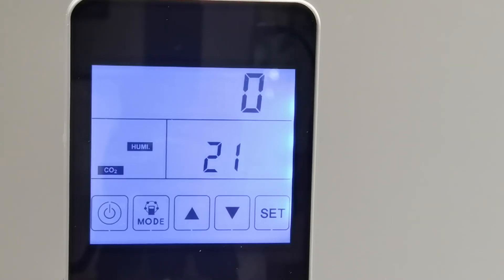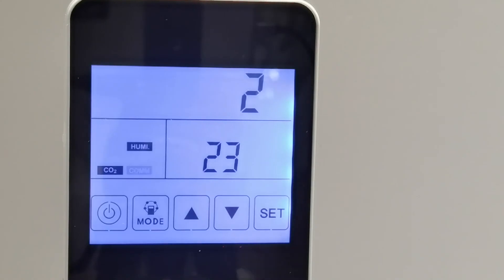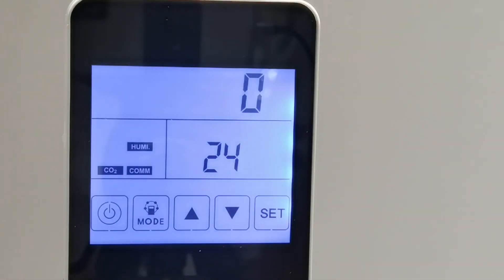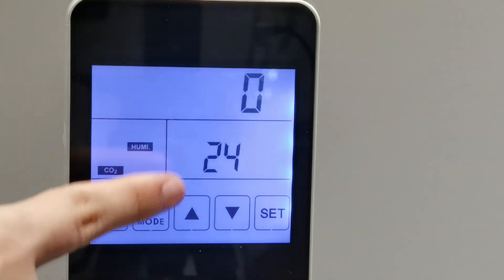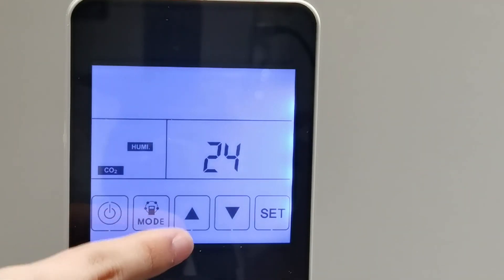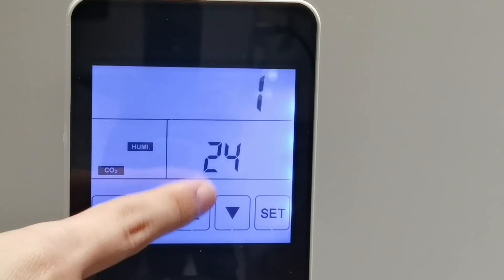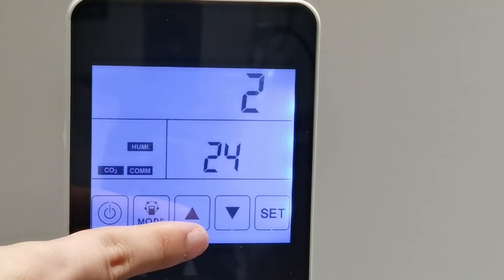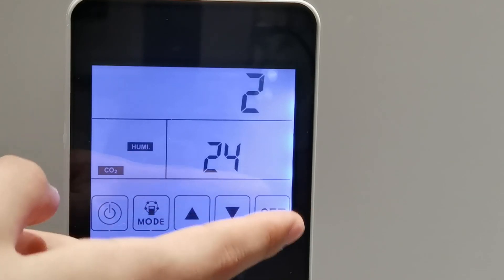Parameter 22 is empty. Parameter 23 refers to fan speed control — this function is already set before the unit is shipped, so end users do not need to do any setting. Parameter 24 is the multifunctional setting: value 0 is reserved, value 1 is to clear the filter alarm, and value 2 is to clear the weekly timer.